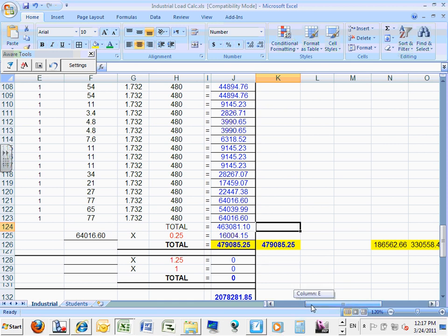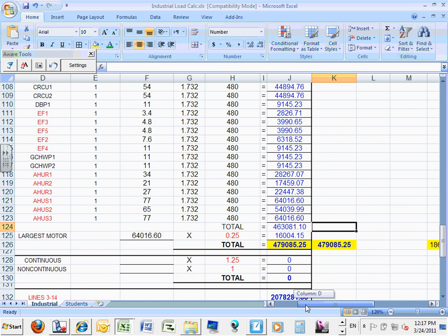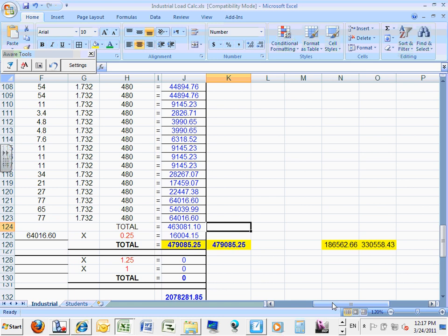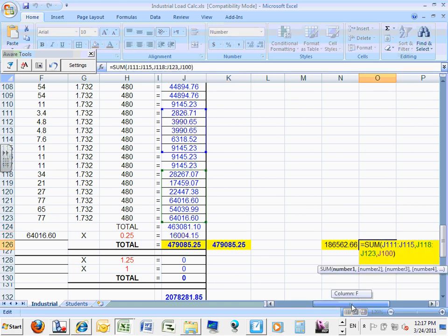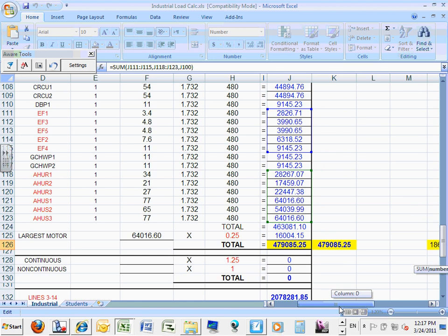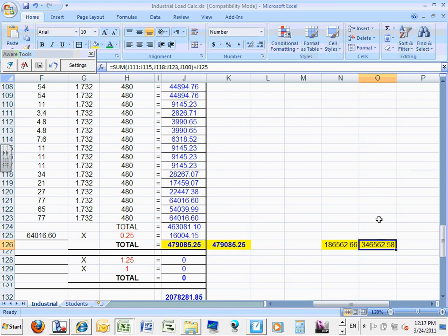So we're really missing a small amount of volt amps, 25%. Which panel is that on? And you know what? Actually, because the largest motor happened to be in the second panel, it's really accommodated to the second panel. So if I want to make sure of this, can you guys do me a favor? If you want to make this proper, you might have to go to this cell and add plus that 25%, the large motor 25%. So I just added 25% for that.